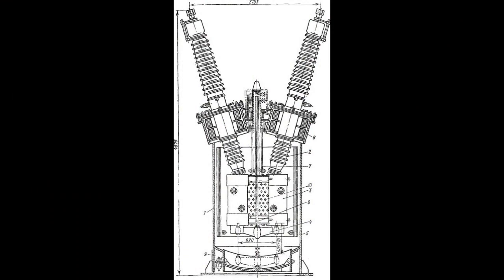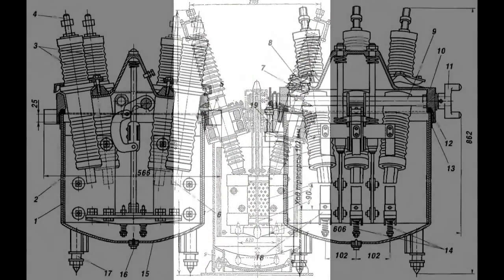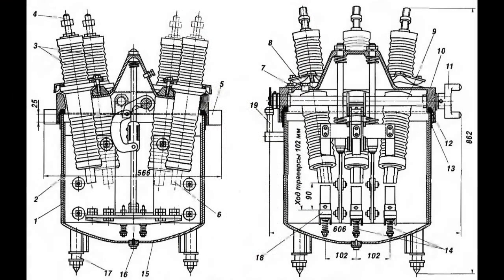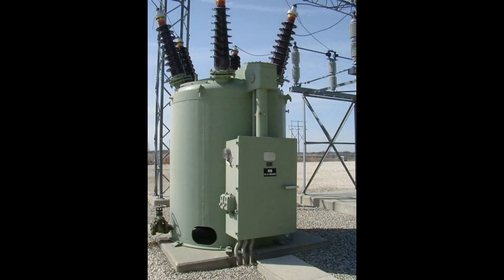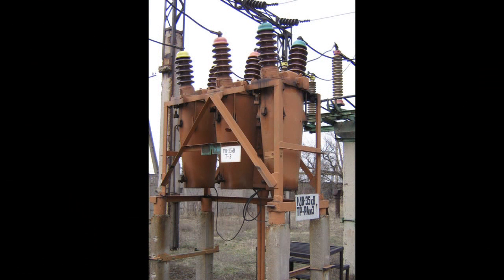Manually or remotely operated single-tank circuit breakers are used at voltages ranging from 3 to 20 kV. Automatically or remotely operated three-tank ones are used at voltages of 35 kV. The latter also have an automatic reclosing function.